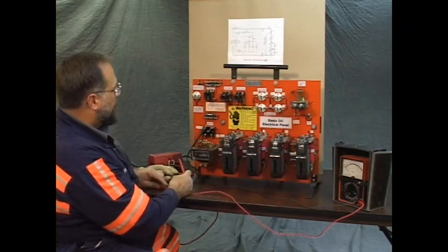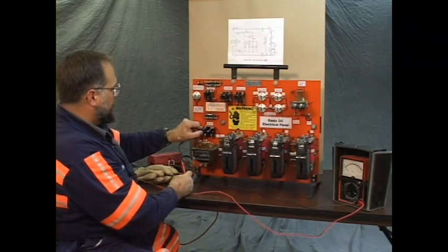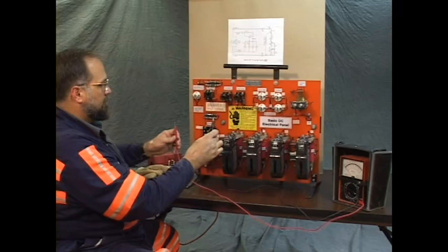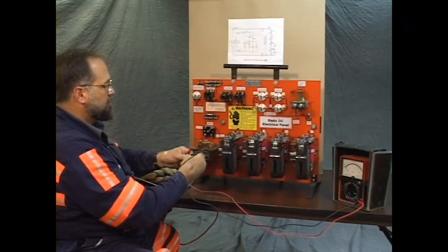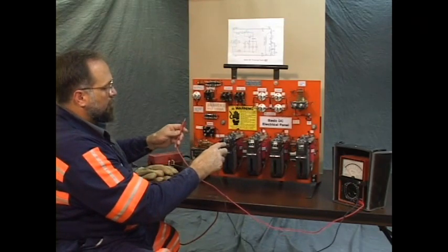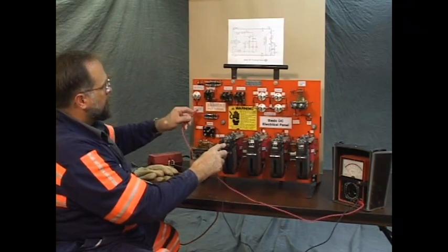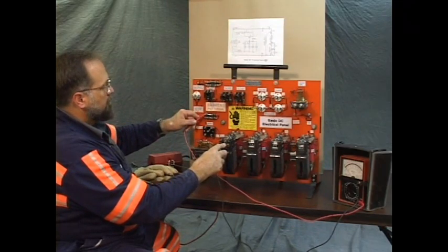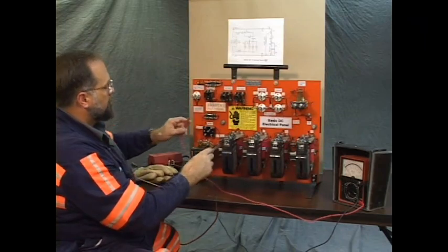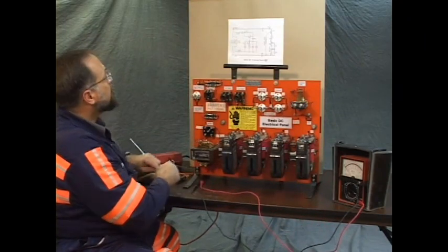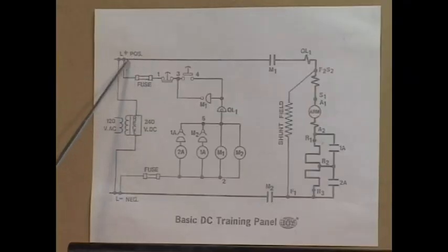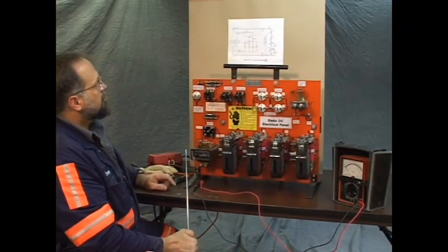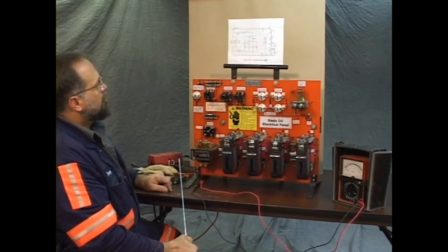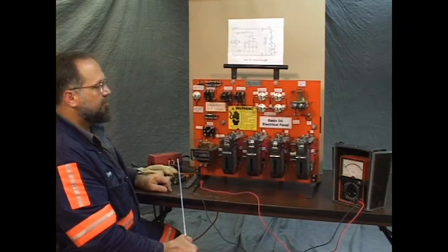Let's pinpoint that a bit farther. We'll remove the lead and test only the wire we suspect. We'll go from the top front of M1 to the line side of the positive fuse, and I have no circuit. So the apprentice could mark his print in the test right here and list that as wire open from top front of M1 contactor to line side of positive fuse.